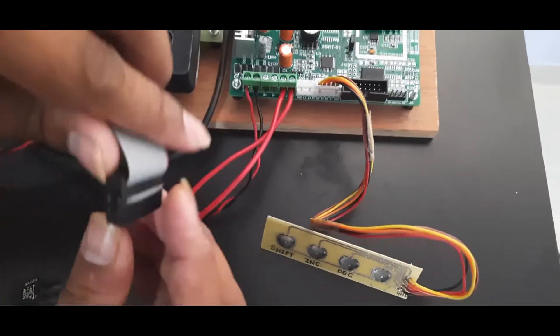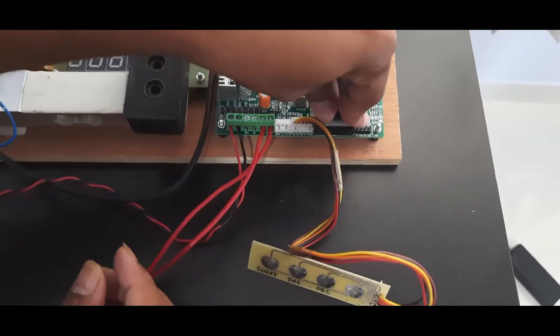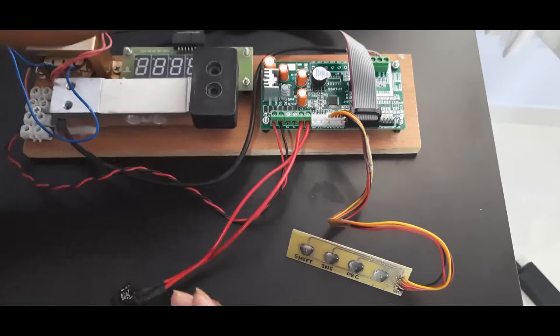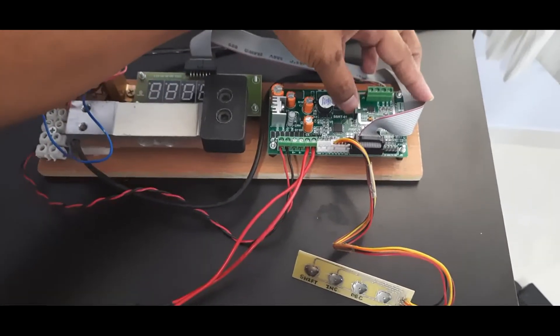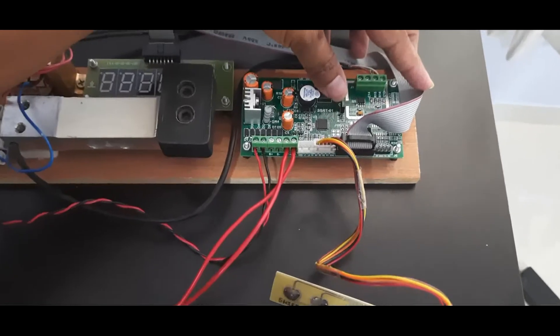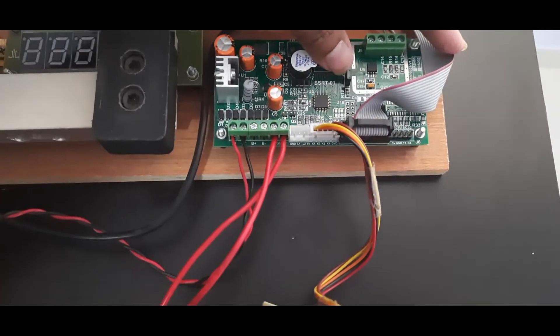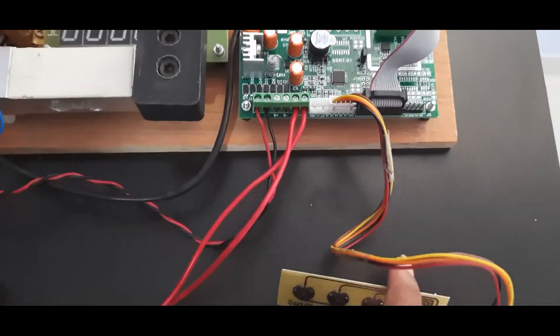Before that, you should make sure this jumper is connected here. This is calibration or hardware access. If it's not connected, it will not go into any setting menus.